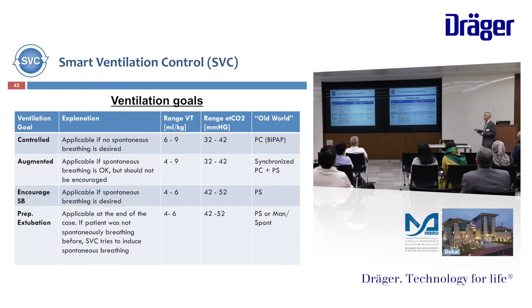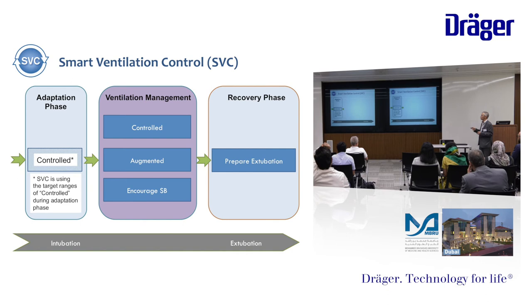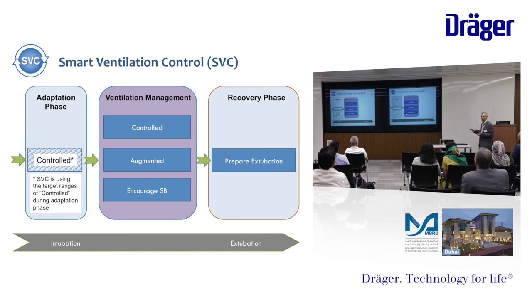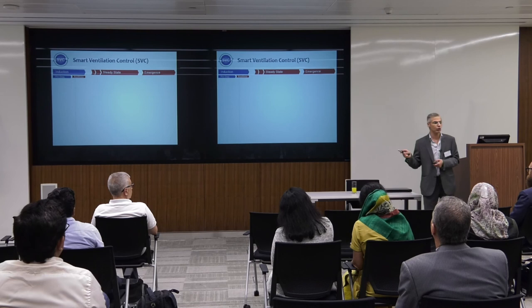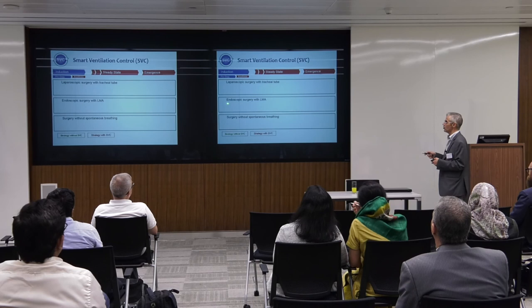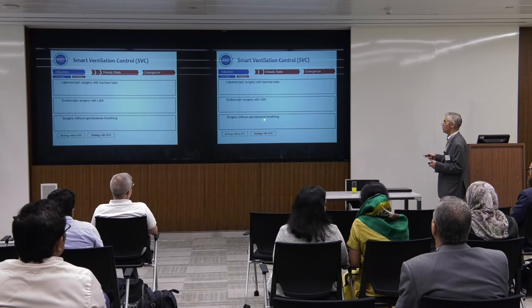Encourage spontaneous breathing — automatically, the end-tidal CO2 default setting is higher, equivalent to pressure support. And finally, prepare patient for extubation — I want the patient ready for 100% spontaneous breathing, equivalent to pressure support or manual spontaneous breathing. Just imagine: at the beginning I need the patient 100% controlled. During the operation, I can change between controlled, augmented, or encourage spontaneous breathing depending on the type of surgery — laryngeal mask or tube, long surgery needing muscle relaxation. This comparison is between smart ventilation control and current practice in three kinds of surgery: laparoscopic, lower GIT endoscopy with laryngeal mask, and surgery without spontaneous breathing.